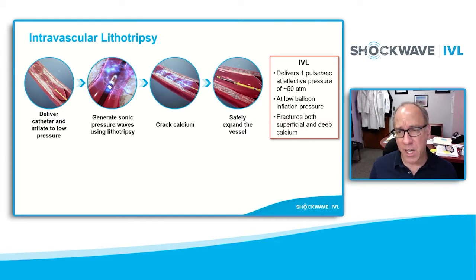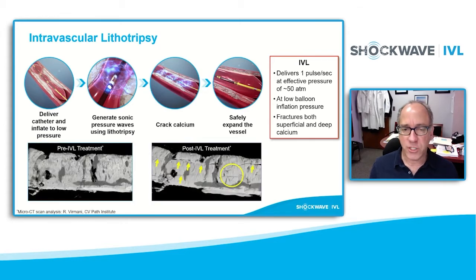And then a series of treatments, which is the submission of this ultrasonic energy into the vessel wall, happens for approximately 30 seconds. At this treatment point, the calcium is fractured, it's made much more compliant, and then the balloon can finally be inflated to its rated or even burst pressure to achieve uniform luminal gain within the vessel wall.